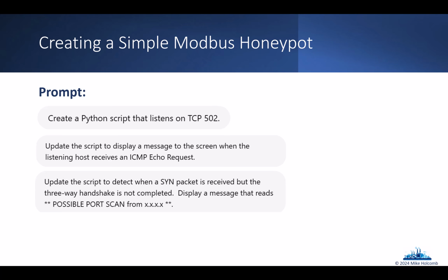And how often do you have legitimate people, operators, and technicians in an OT environment doing port scans? You shouldn't. So if you see potential port scan activity, sure, it could be a busted connection, but more than likely, yeah, it's a port scan. And yeah, it could be a technician that just found how wonderful Nmap is and is using it, which they shouldn't be, but maybe it's an attacker. ICMP, maybe it's an attacker, probably not. Port scan activity could be an attacker.